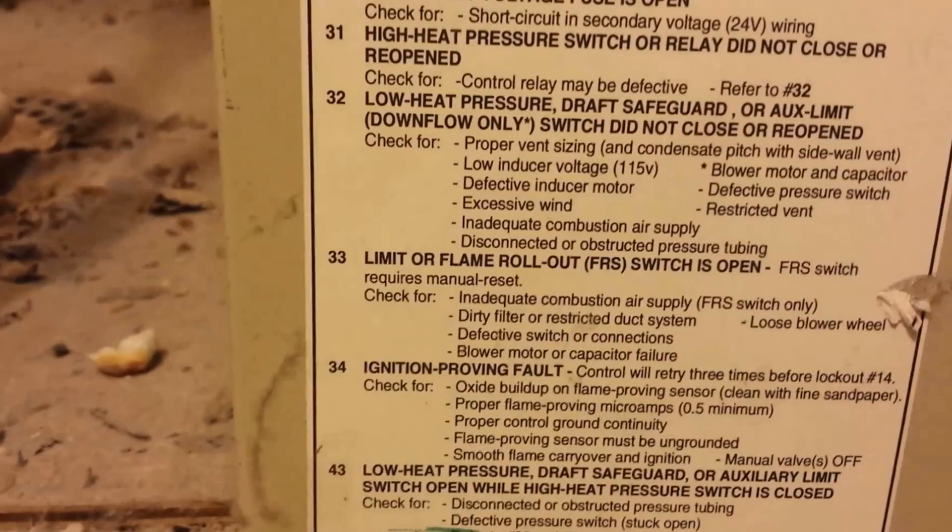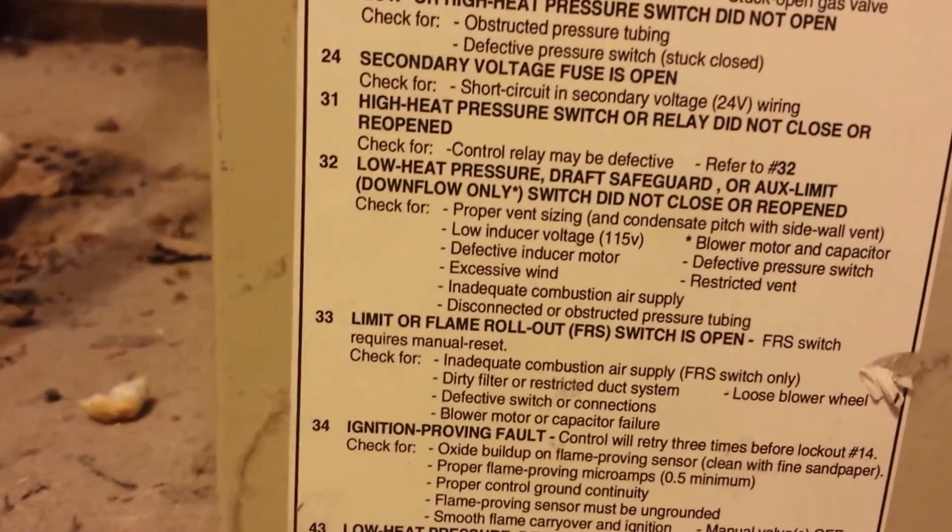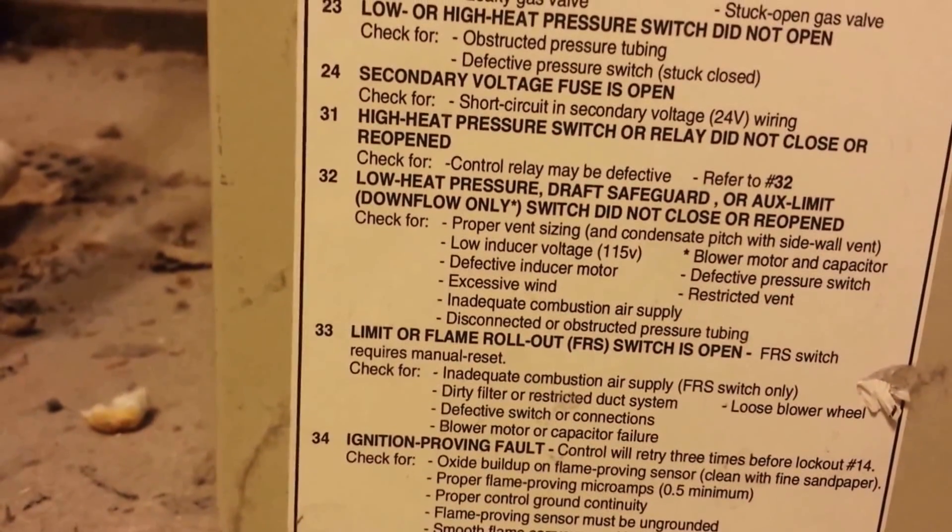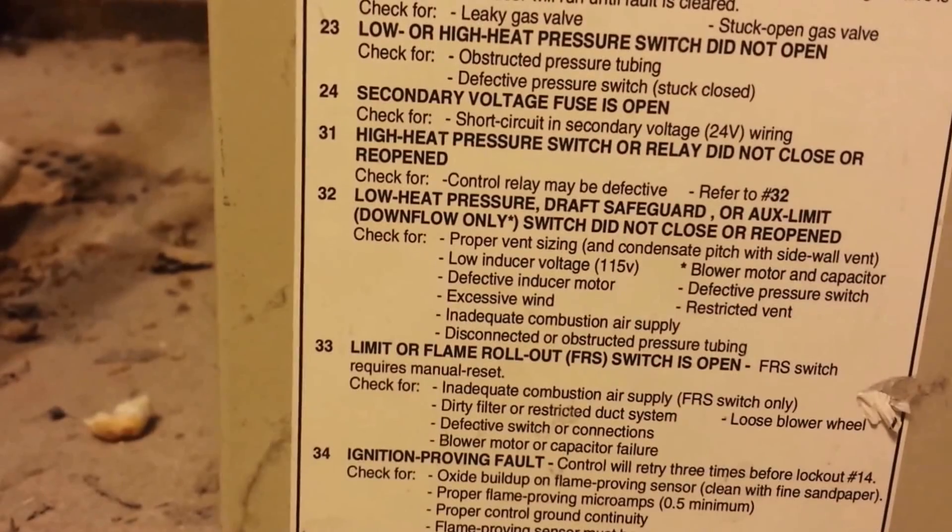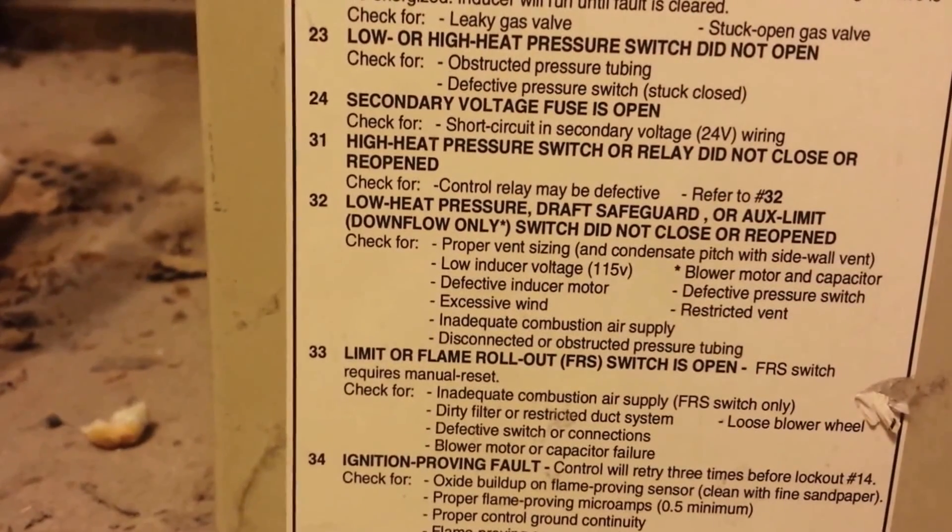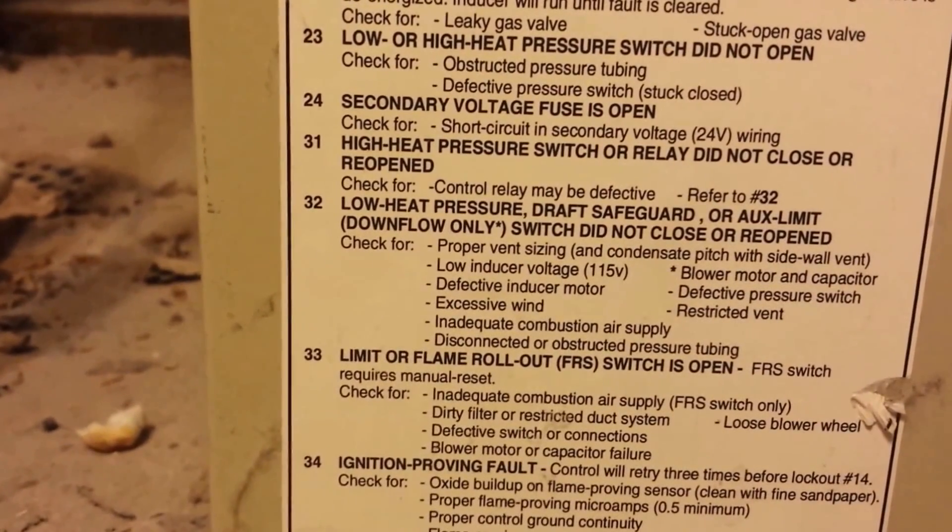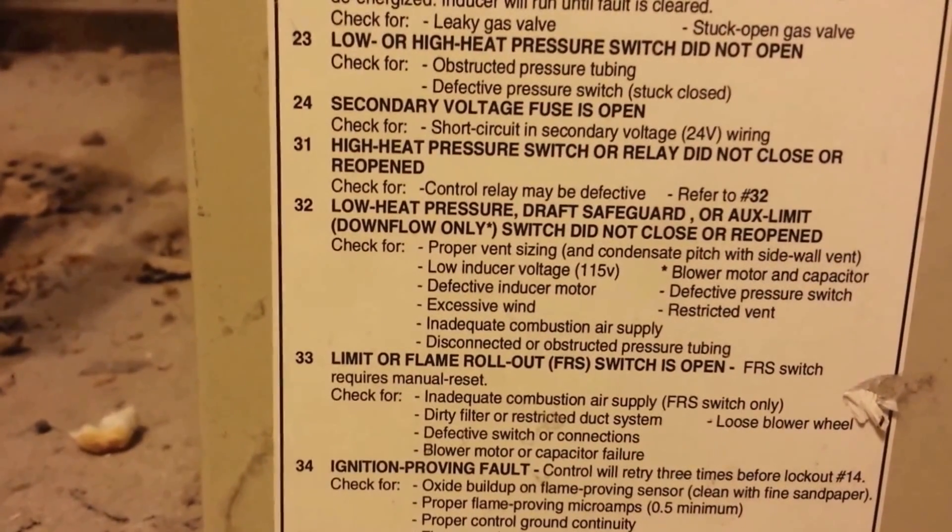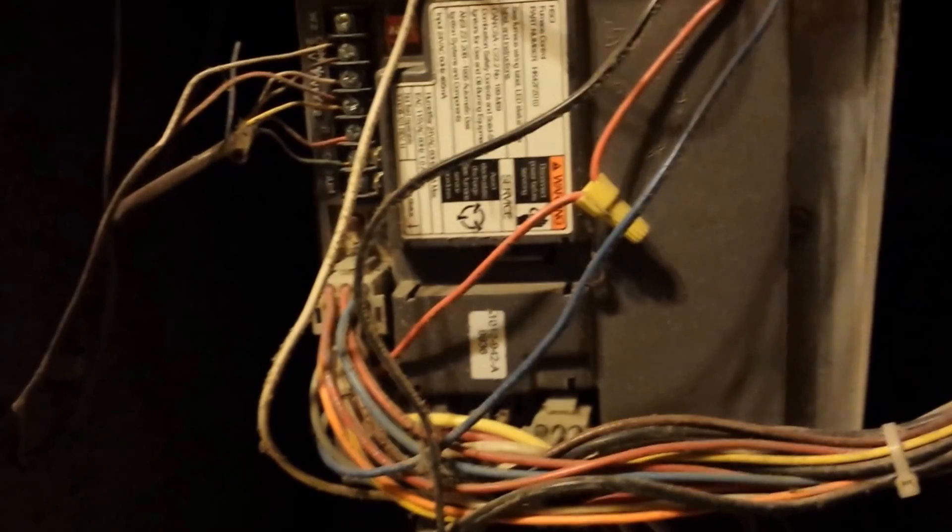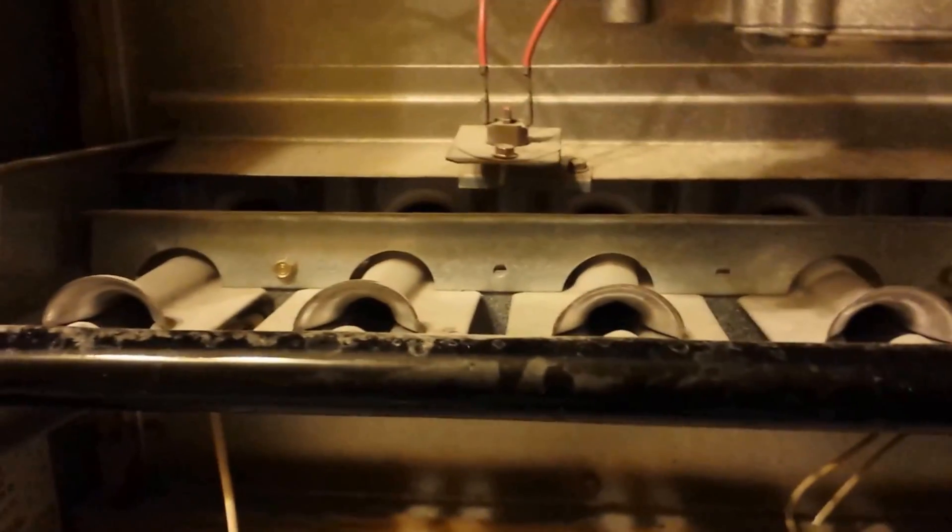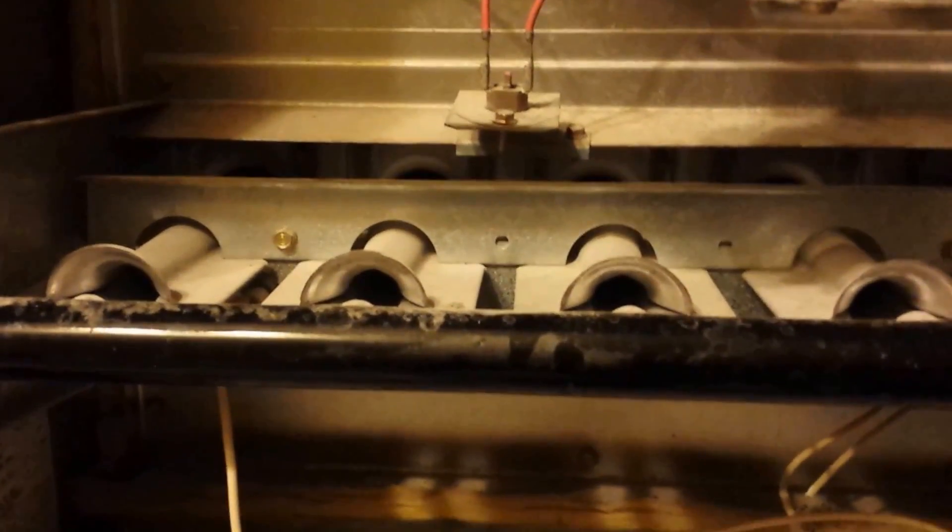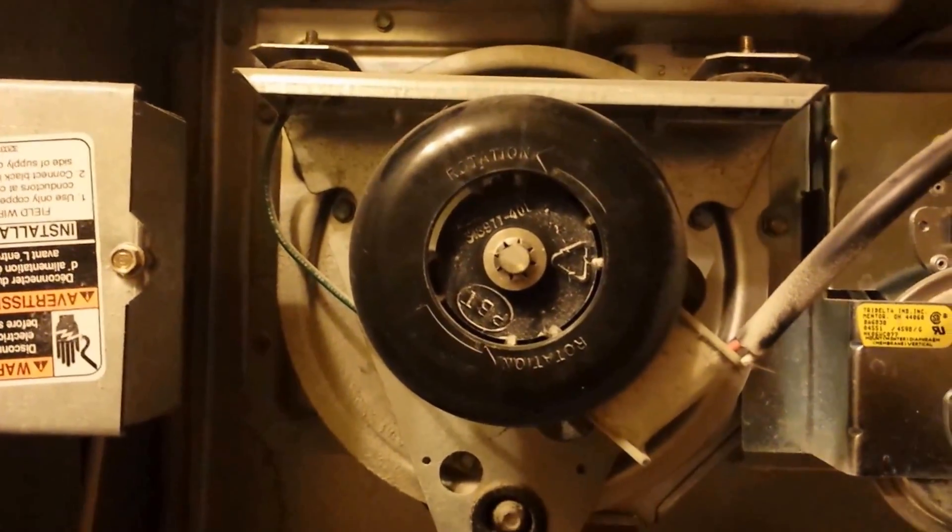That happens if the flow of air is restricted. The most likely cause is if your filter is dirty. What will happen is the blower will kick on and it will run, but you'll never get your flame to ignite. So this will never be igniting and that guy will never be spinning.